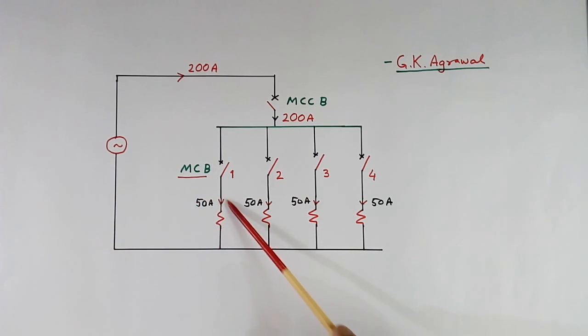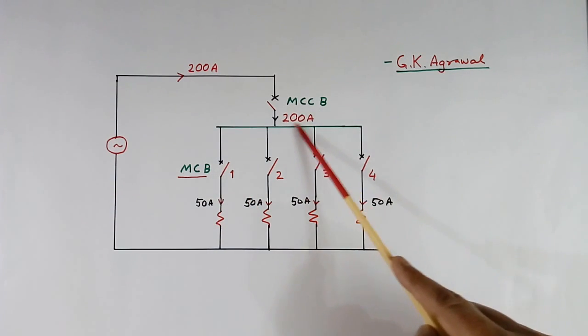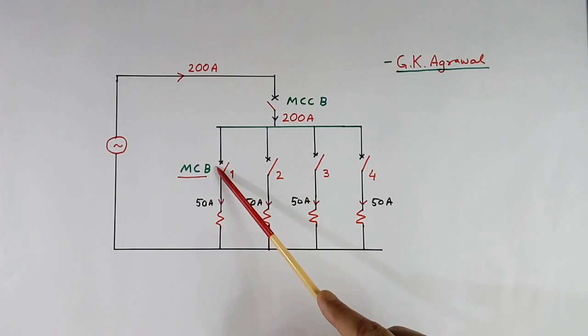Now suppose a fault happens here. This MCB will trip first. The MCCB will not trip; this is rated for very high current. So the MCB will trip, so there will not be any problem. All these three loads will work properly.